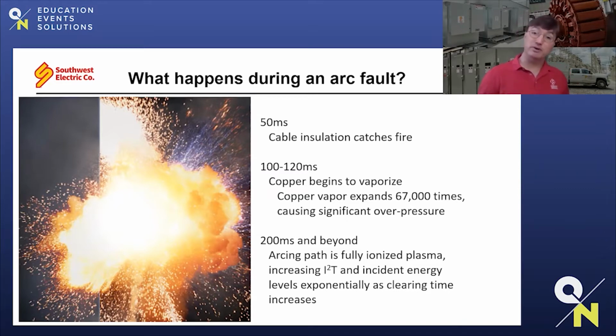After about 100 to 120 milliseconds, the actual solid copper conductor will begin to evaporate. Now, when water changes from a liquid to a gas, when it boils, it expands about 1,000 times. When solid copper evaporates under this intense heat, it expands 67,000 times. You can just imagine the amount of overpressure that occurs. That's why you see this explosion. That's why you see shrapnel generally from these kinds of arc events, because of that overpressure when the conductor evaporates. And afterward, you usually don't see a conductor. You usually see melted slags of remains.